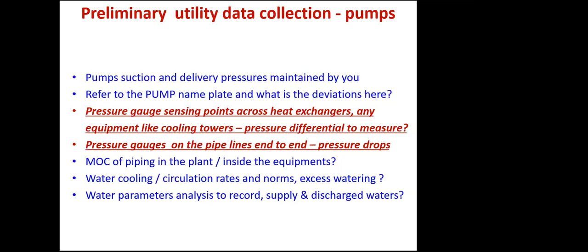Like that, see the water norms: excess water that is pumped in the industry is also lost to the industry. If you are using excess water, your circulation water is more and your pumping pressure is more, it is all excess. Excess means excess kilowatts, excess water consumption, and problems like water hammering in the wet part of the system, which is also a loss to the system. Optimize your pressure, that is more important. The water parameters, the TDS and the hardness, have to be monitored routinely and maintained, especially in the summer months. Next, please.